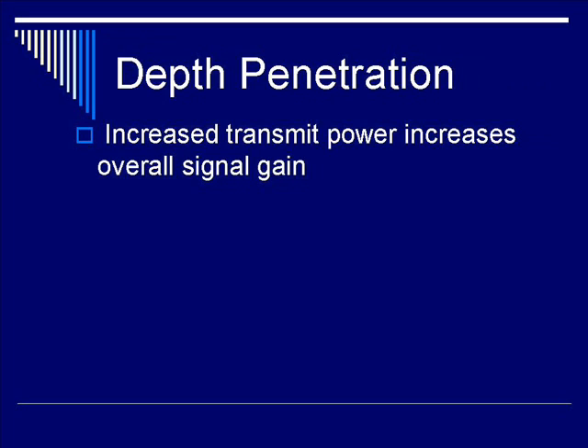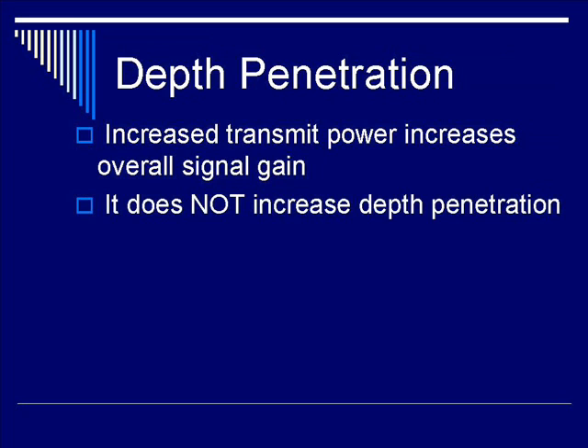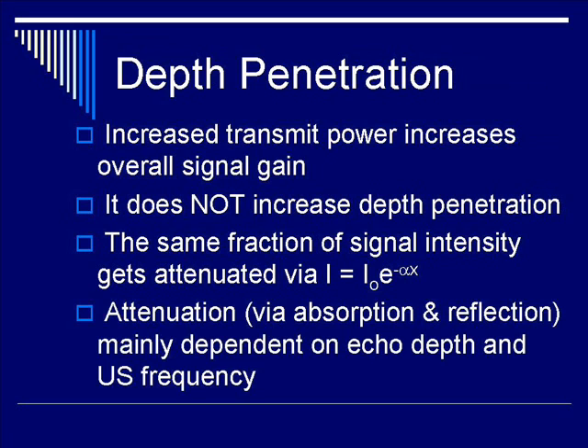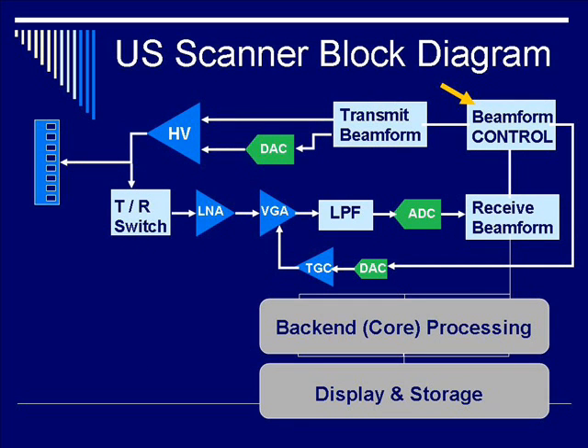When you increase the transmission power, you increase the overall signal gain, albeit with increased patient exposure to acoustic waves. However, increased transmission power does not increase depth penetration. Signal intensity degrades exponentially according to the equation I = I₀ × e^(−αx). So with more power, the same fraction still degrades. Attenuation is mainly dependent on echo depth and ultrasound frequency — attenuation determines penetration — therefore transmission power does not play a role.